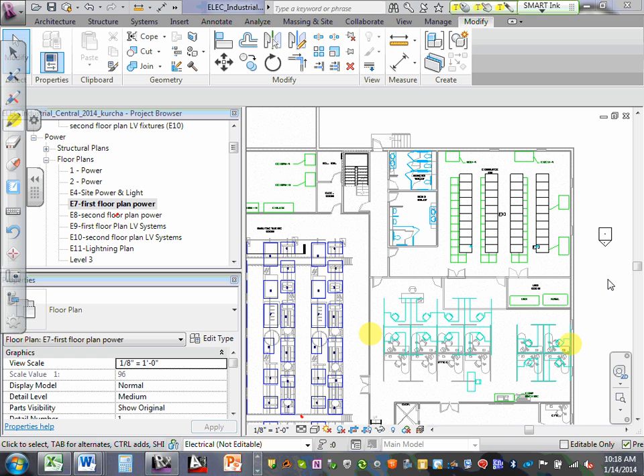That's if you're using 110 strobes. Okay. If you're using a 30 candela strobe, that's basically just 30 foot by 30 foot. Okay, so this template says right on here your candela ratings and your spacing requirements.